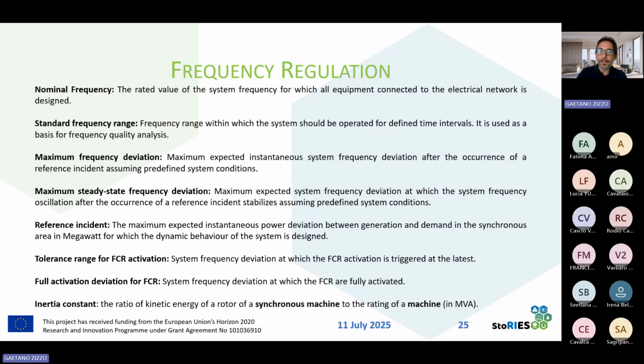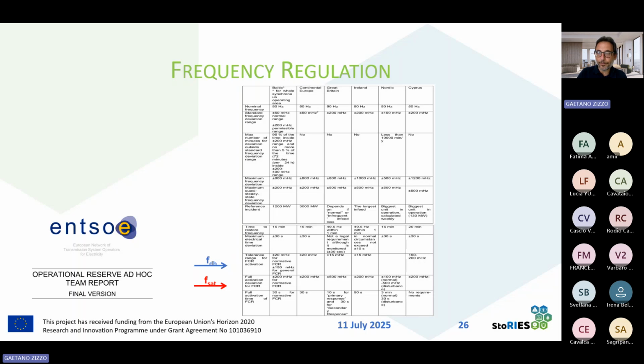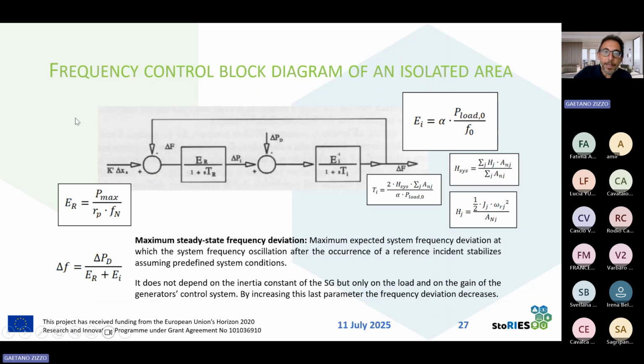These are some definitions taken from ENTSO-E documents. These are some values from ENTSO-E, and let's refer to this scheme. Here we can see the classical representation of a single area system, where we can distinguish the regulating action of power plants during a power disturbance, an active power disturbance, that is this one, delta PD, and this represents the action of thermal power plants, hydropower plants participating in the primary frequency regulation. The power plants participate considering the maximum power they can deliver, their active droop, and with this formula that represents the power energy characteristics of the power plants.